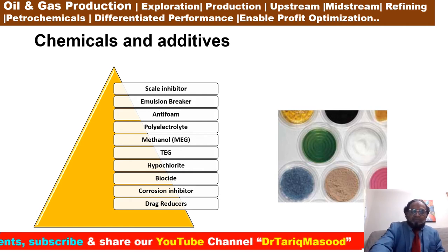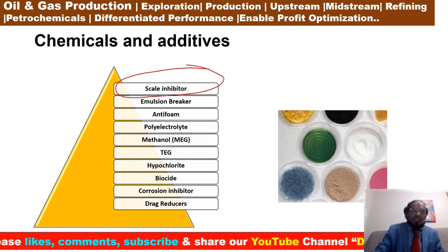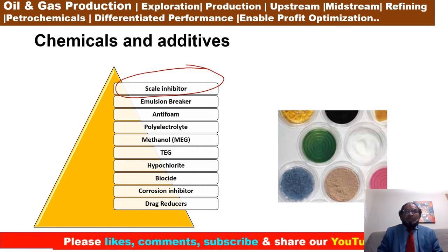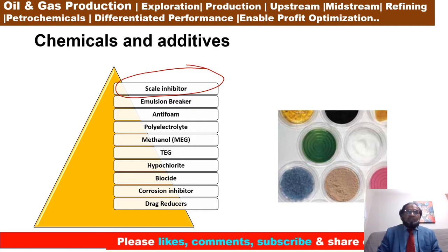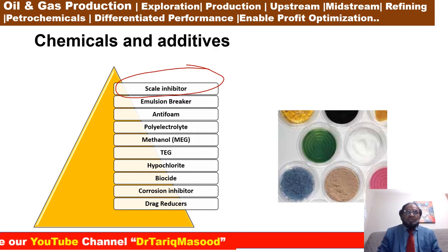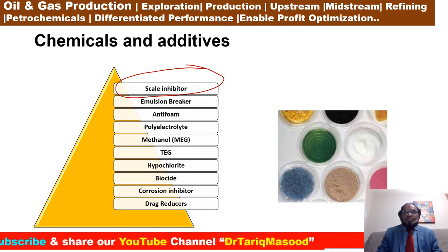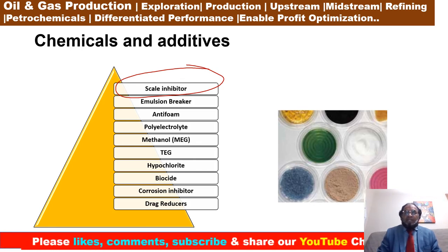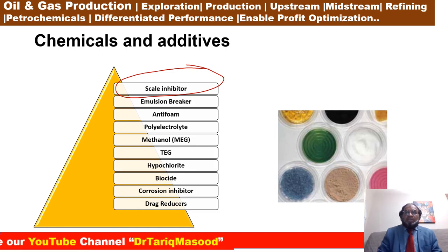The first is scale inhibitors. What is a scale inhibitor basically? The well flow contains several different contaminants such as salt, chalk, and traces of radioactive materials. As pressure and temperature change, these may precipitate and deposit in pipes, heat exchangers, valves, and tanks. As a result, they may clog up or become stuck. The scale inhibitors prevent the contaminants from separating out. A scale or sedimentation inhibitor is applied to the wellhead and production equipment.